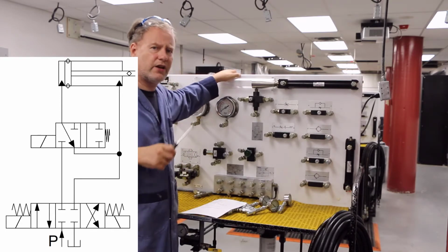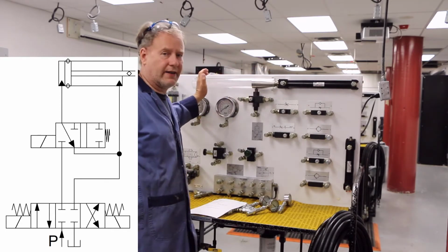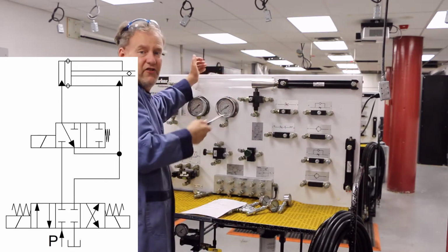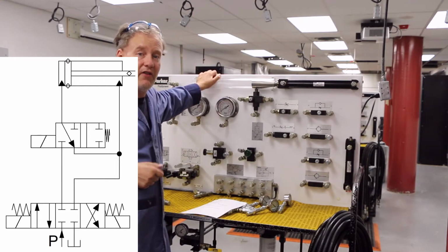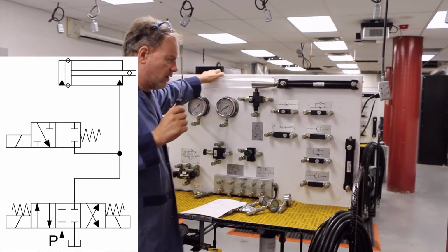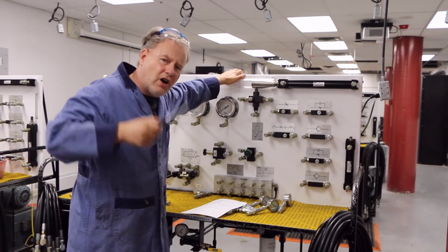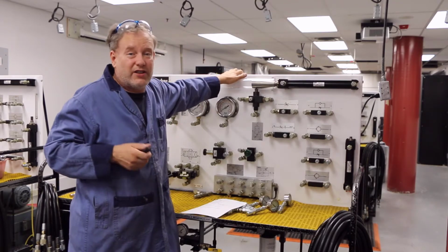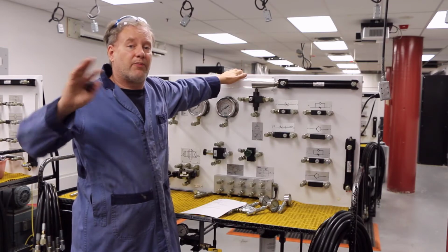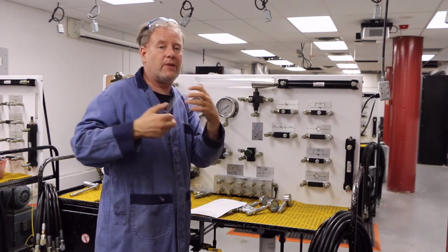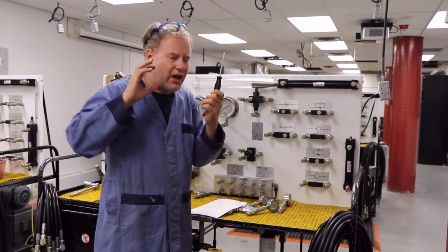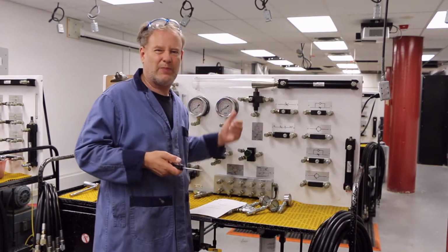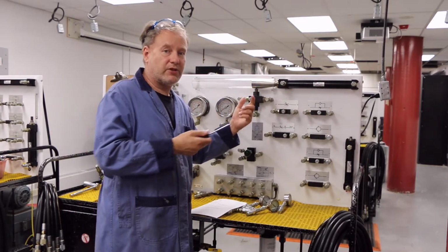Now, it actually creates a bit of a problem when this thing gets all the way to the end, because if I'm regenerating this fluid, I'm not going to generate much pressure or much force in here. So what we do is we shut our regen valve off when this thing extends all the way. There are a few different ways that we can do that, but we won't talk about how to turn it on and off. That is a control thing that you can figure out with either some kind of pressure sensor that's going to switch your valve, or maybe some kind of limit switch. But we're not going to focus on that. We're just going to see a regen in action. So we're going to hook this thing up normally, watch its speed, and then we're going to hook a regen up to it, and we'll see that it goes a lot quicker.